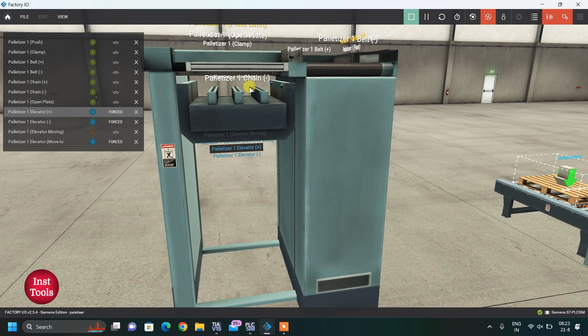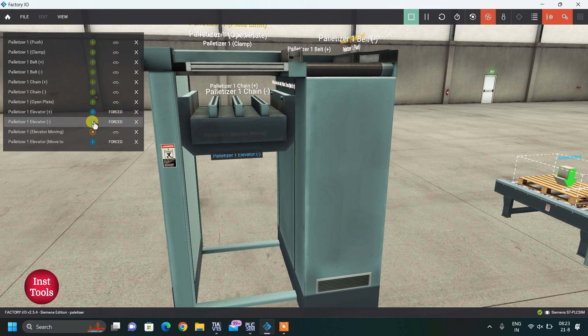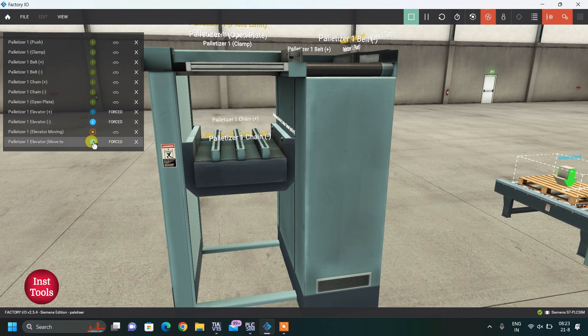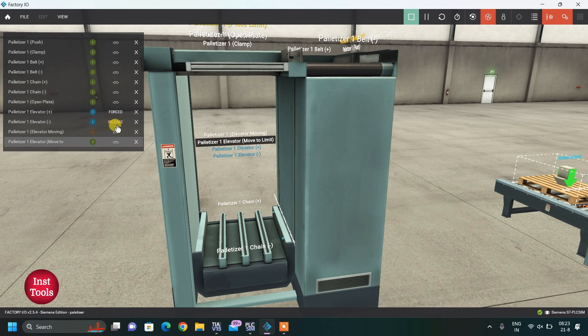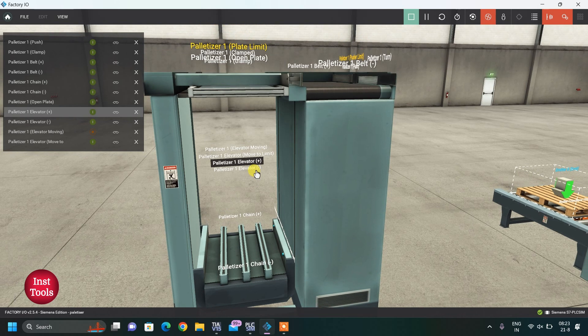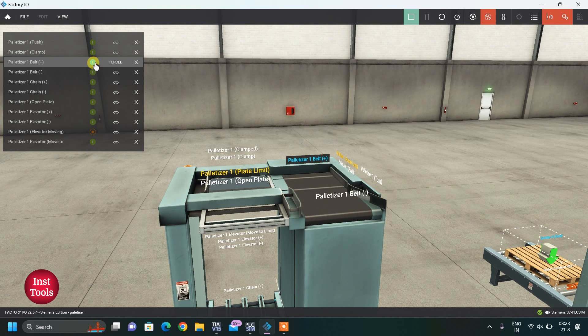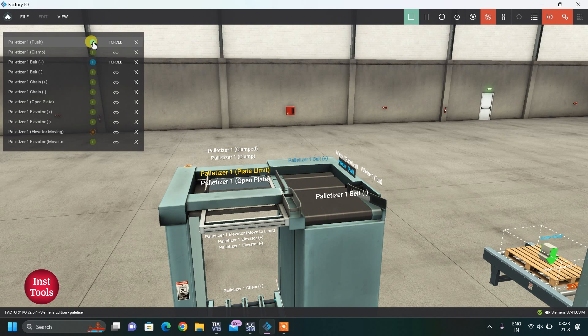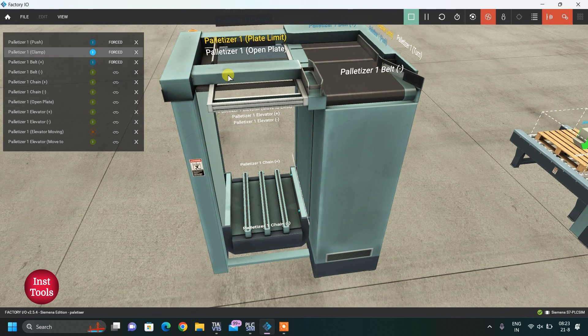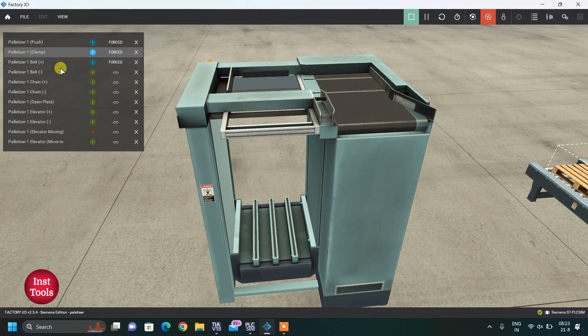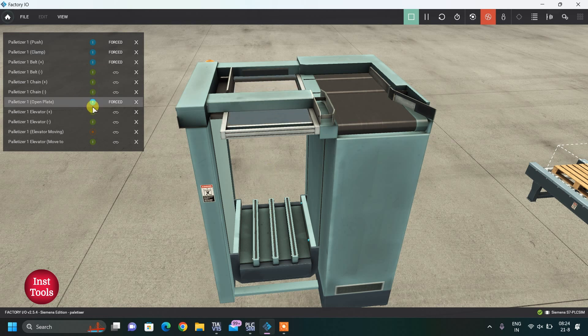When one layer of boxes is stacked, you move the elevator one step down, then another step down, then a third step, and finally all the way down. These are all digital outputs only. The palletizer belt conveyor moves in this direction — we stop it when boxes are in position and turn on the pusher. When the output is on, the pusher goes forward; when off, it moves backward. When six boxes are here we clamp them — you can see the clamp and unclamp operation.